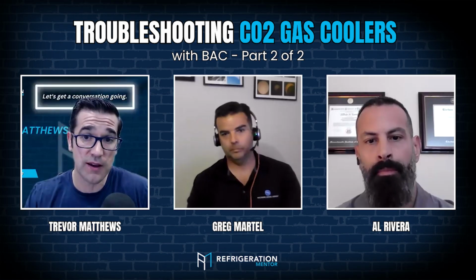Yeah, for sure. Because we always want to keep it below the critical point as much as possible. Subcritical. And then in the winter months, we don't want it to run too low. Like you guys said, we've got that holdback valve, and that comes into play with the gas cooler to make sure we don't get too low, because if we get too low, then we get oil issues and compressor issues, which you guys probably get called for. It's like a gas cooler issue, but actually it's not necessarily a gas cooler issue.